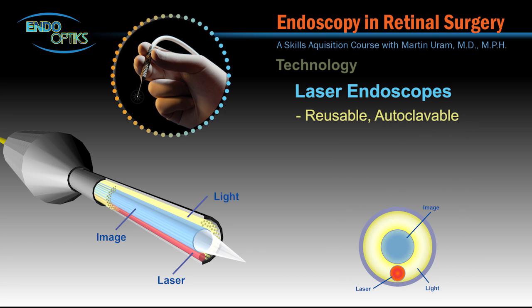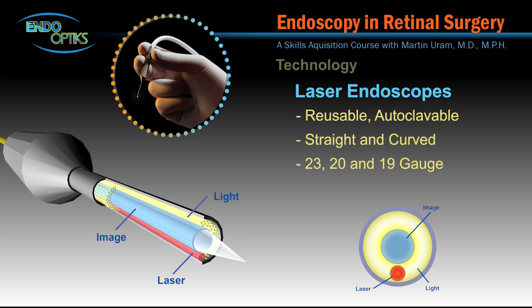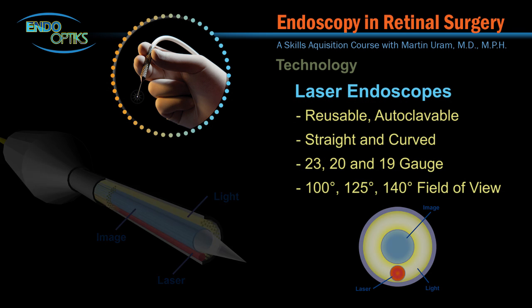These instruments are comprised of a central core of fiber optic imaging fiber, surrounded by a number of tiny light fibers and one embedded laser fiber. Depending upon the surgeon's requirements, they come in a variety of configurations, including straight or curved, 19 to 23 gauge, and various levels of resolution and field of view.